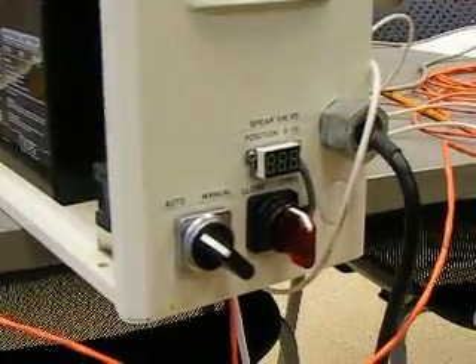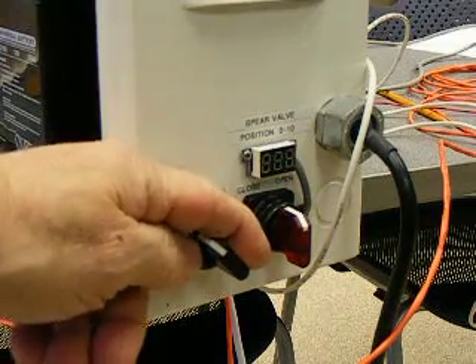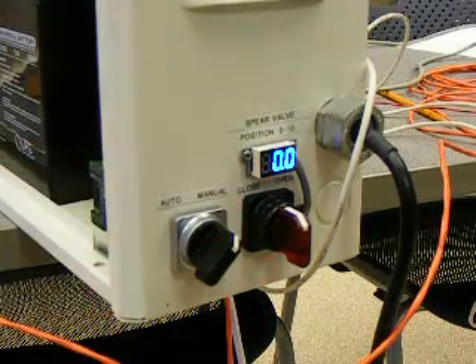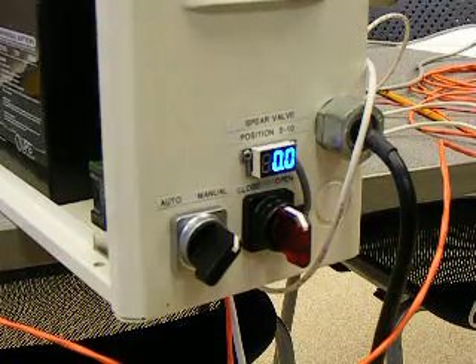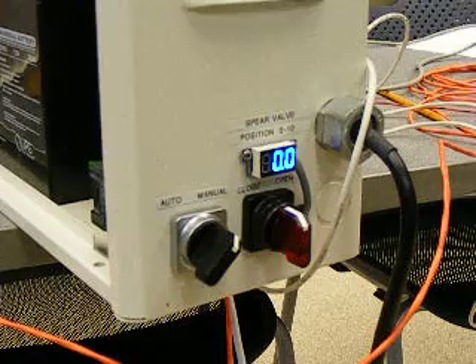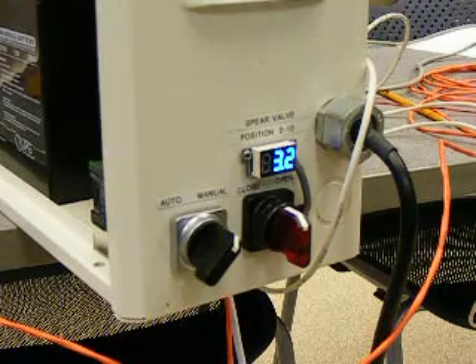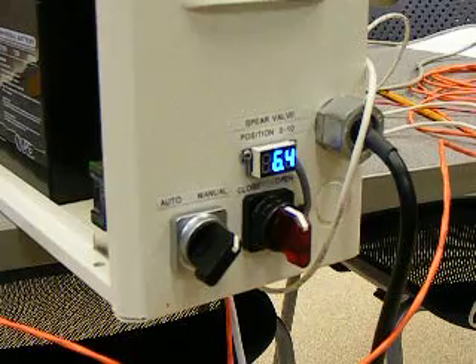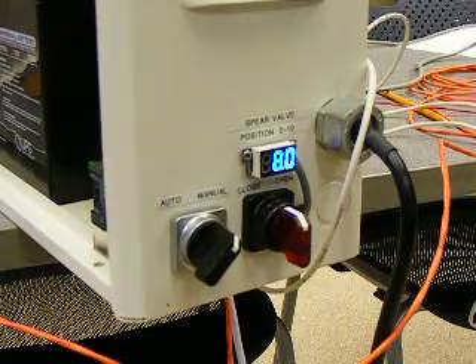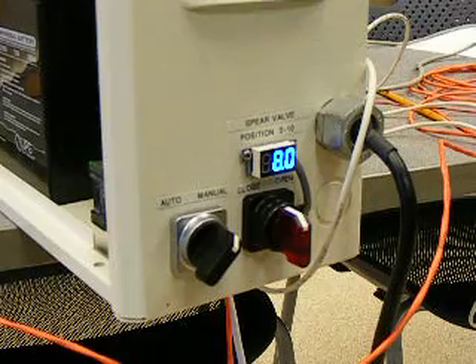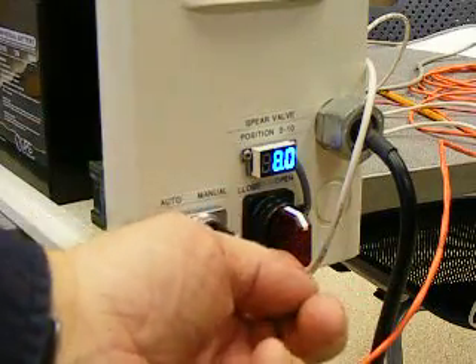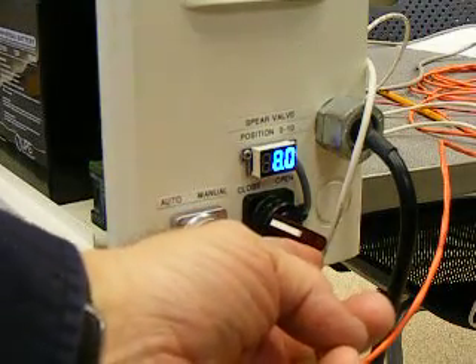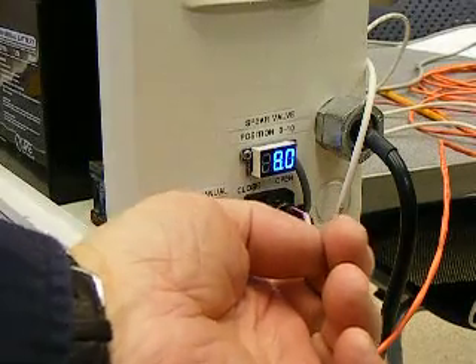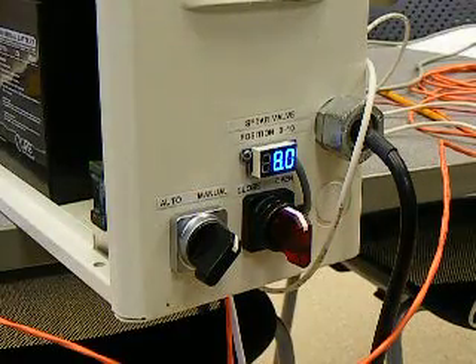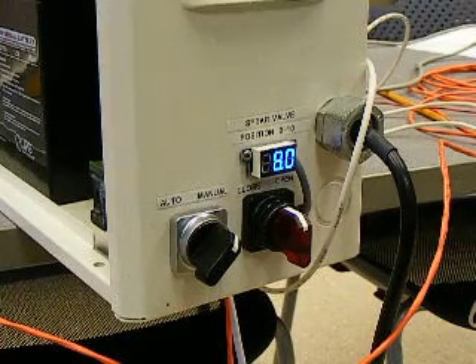Move the camera here. There is a manual control for the system. So if you're down at the generator and you want to put it in manual and manipulate the position of the spear valve, the readout there, which if I go over and slide the magnet, you'll see it change. So you've got 10 units of graduation, actually 100 units of graduation there across a 2-inch range, and then you can modify the valve position by just simply switching here for close, go to the other side for open, and that bypasses the data acquisition module and directly fires the relays.